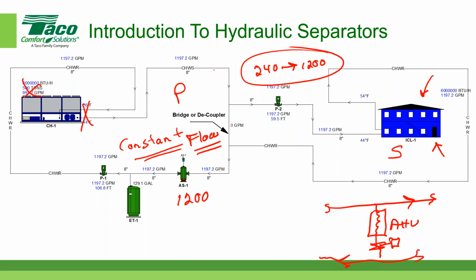So as I said a moment ago, case number 2 is when the secondary flow is less than the primary flow, and that typically happens as you back down from your peak demand. In our case it was 1,200 gallons per minute. So if the load was anything less than 1,200 gallons per minute, then we'd have a reduction in flow, and that's when the primary is always greater than the secondary. Does that help answer that? Yeah, and based on what we've talked about in the past, and you have stressed more than once in other presentations, that's most of the time.